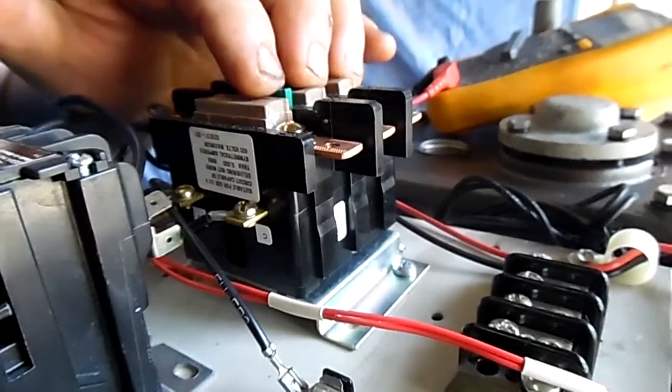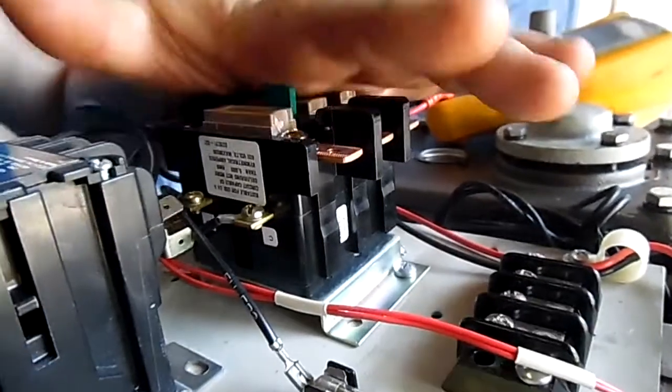and see why your heater is going. It could be the heater itself going bad, or your motor's drawing too many amps and it's trying to protect itself by shutting down.